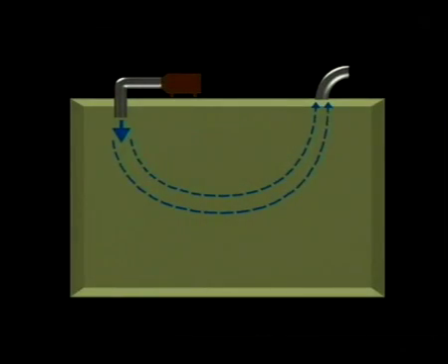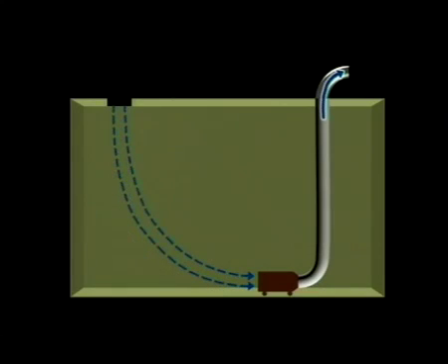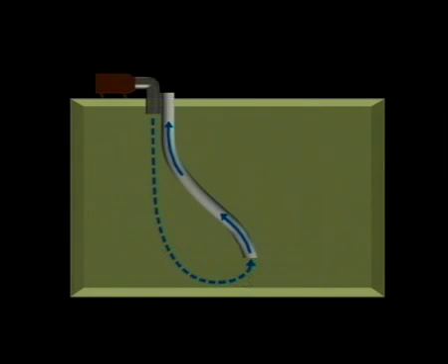The placement of exhaust duct inlets and make-up air inlets is extremely important to achieve proper air distribution. Air distribution and circulation will be improved when air entry and exhaust are accomplished through separate openings. When only one opening to the space is available, air circulation can be improved by extending a duct to the exhaust inlet from the bottom or back of the space.